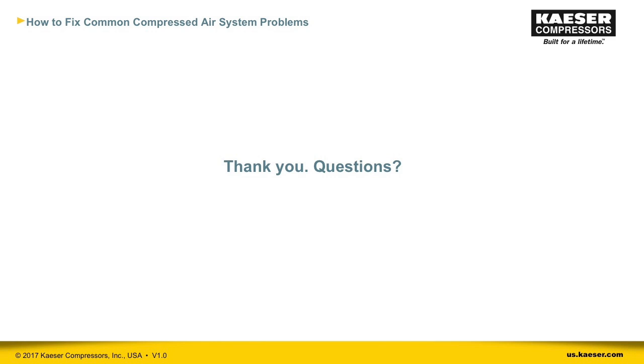When should I use a VFD compressor? Well, VFDs are actually one of my favorites. However, the application of a variable frequency drive or variable speed drive compressor is not a panacea and should not be done willy-nilly, but should be done after careful evaluation of the variance in your system demands, basically your demand profile, and of course also considering your environmental and power conditions at the plant. So again, I would highly recommend to do a system assessment and then discuss this with a compressed air system specialist.